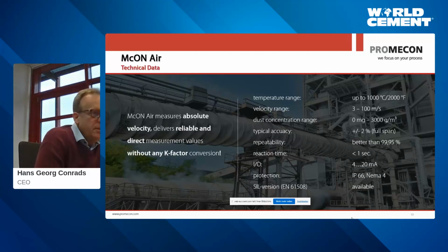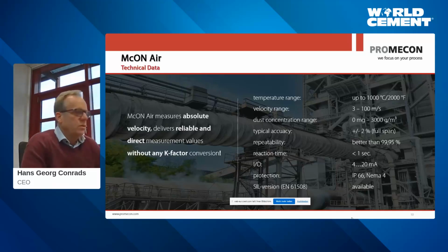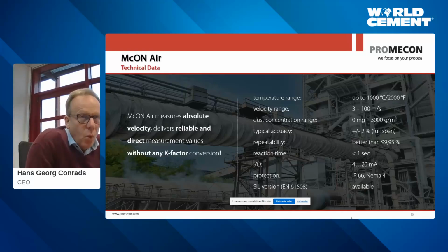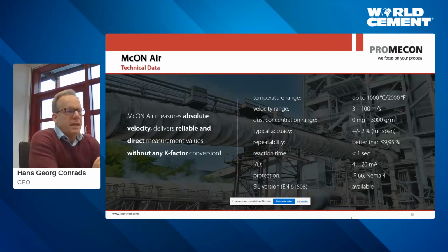There's no other delta P measurement that can show a turn down ratio of that sort. The dust concentration range with the range extender is from 0 milligrams to 3,000 grams per cubic meter. If you don't have the range extender, you should have something like at least 1 milligram of dust in your gas flow, which is usually the case. Accuracy typically is 2% full span.